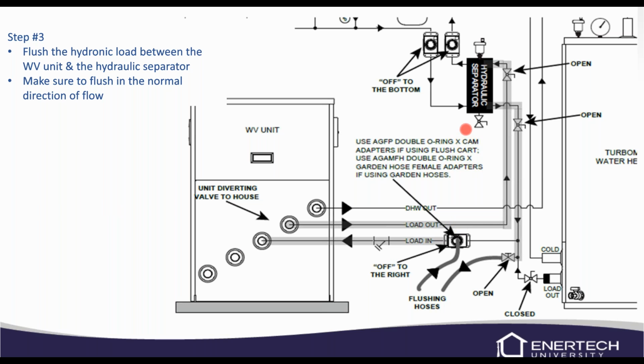Next, here we've got a hydraulic separator in the circuit. So we've got maybe an air handler that's larger than 2 tons. So now we're going to flush through the unit, through the load, through your hydraulic separator, and back to your flush cart.